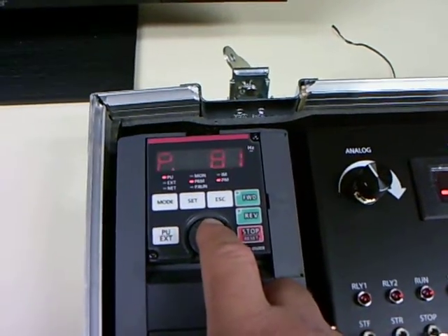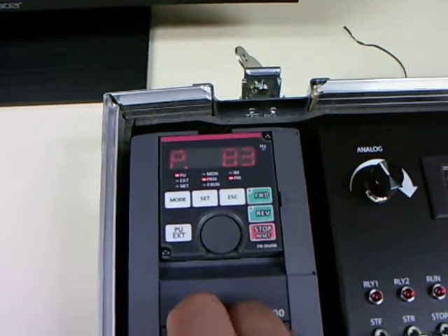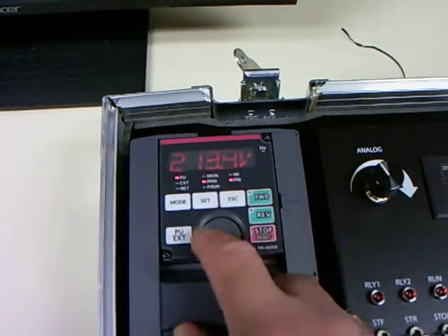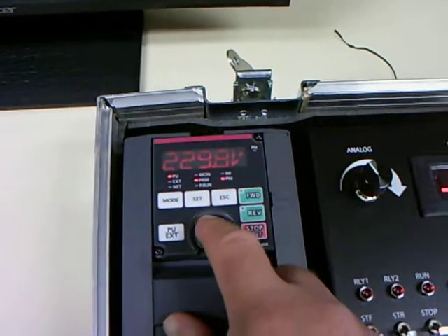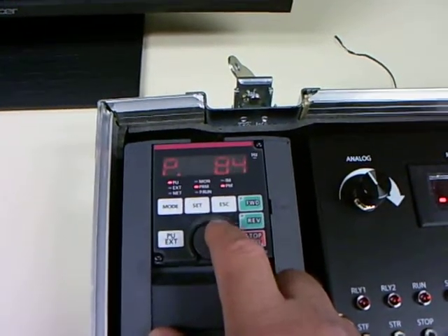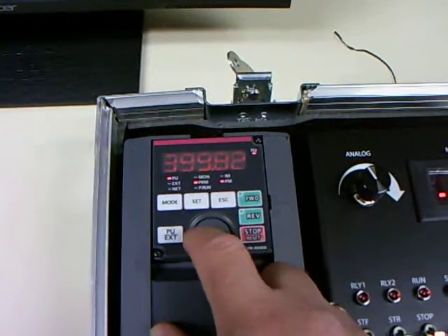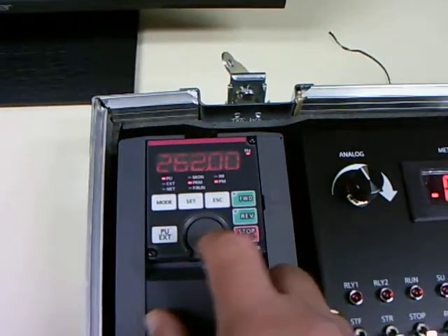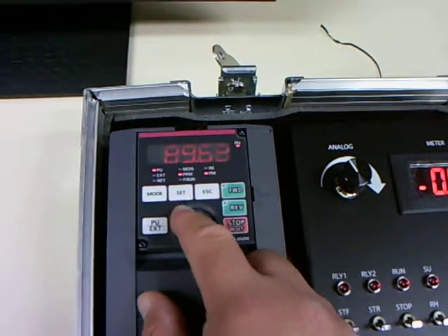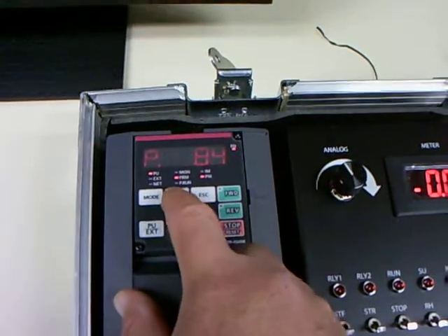The next thing we need to do is set the rated motor voltage and frequency. These are often unusual values with an IPM motor compared to what you'd see with an induction motor. In this particular case, it's a 230 volt motor — nothing special about that — so let's just dial in 230 and set that. And in parameter 84, I'm going to put the operating frequency. It's actually based around 90 hertz, so I'm going to use 90 as my value here and set that in.